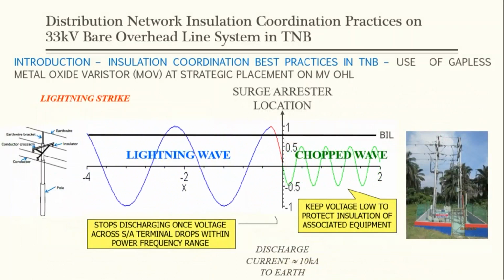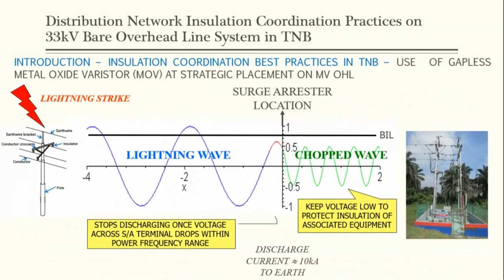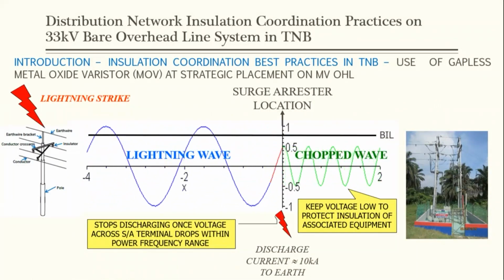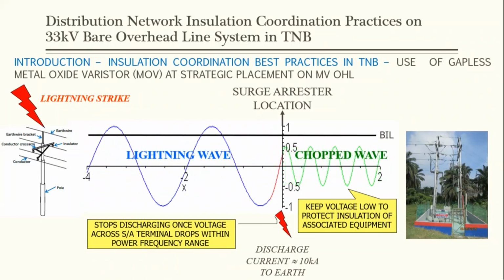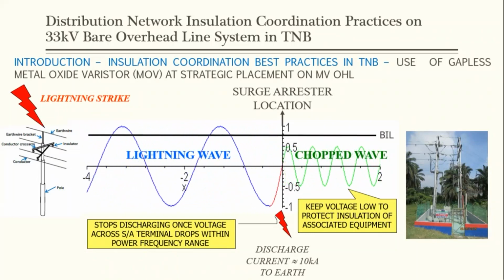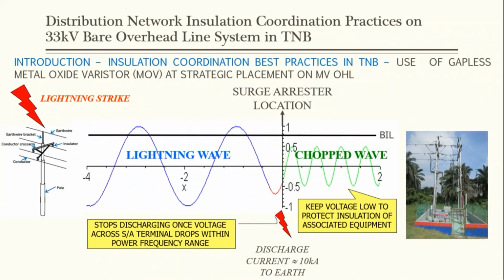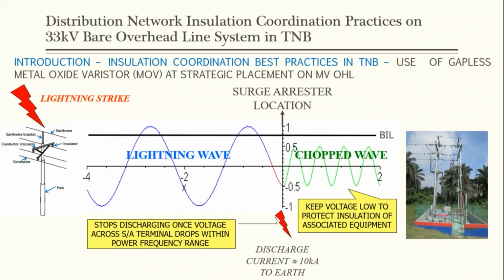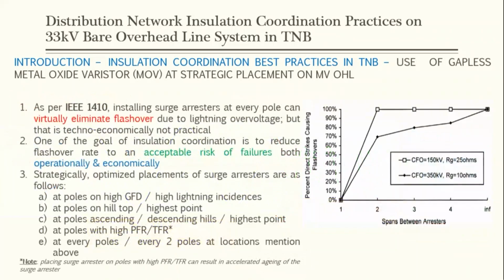So for example, if the lightning strikes, you have a lightning wave higher than the BIL. Once the surge arrestor starts to discharge 10 kA, the product will be a chopped wave or a residual voltage which is below the BIL of the components. So this voltage will be kept low to protect the insulation of associated equipment, for example, auto recloser, load break switch, or even isolator links. And as per IEEE 1410, installing surge arresters at every pole can virtually eliminate flashover due to lightning overvoltage, but that is techno-economically not practical.